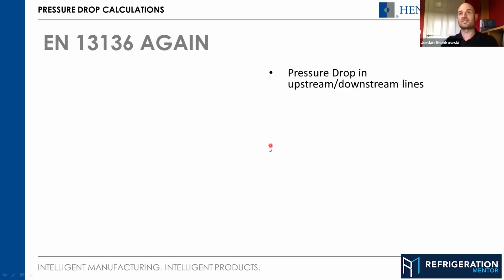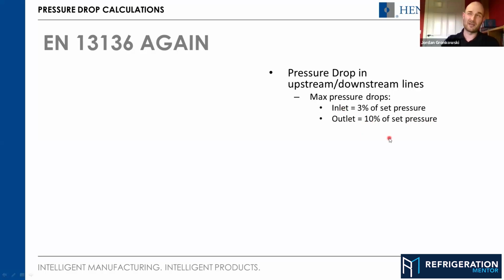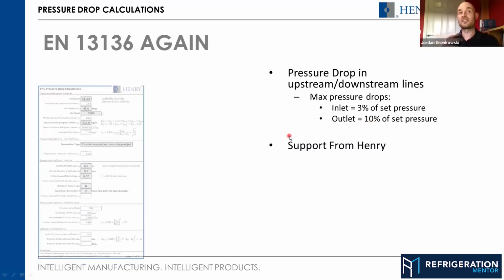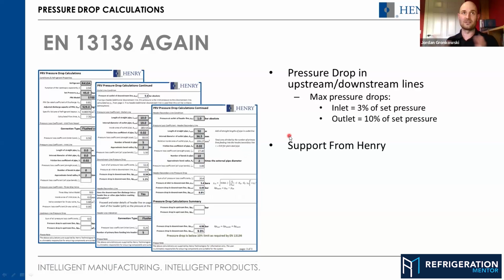But EN 13136, again, there are calculations in there and limits. So the limits from 13136 are 3% of set pressure on the inlet side and 10% of set pressure on the outlet side. If you have a back pressure independent valve, I think that's 20% on the outlet side you can get away with.